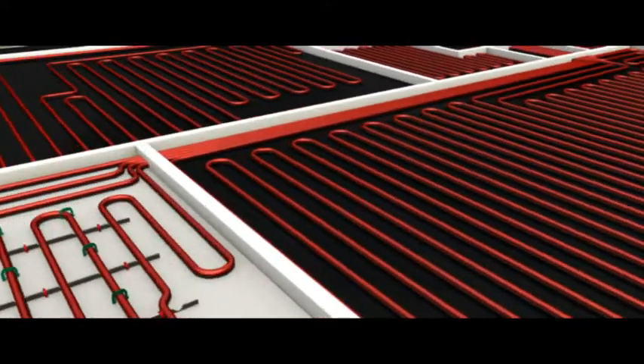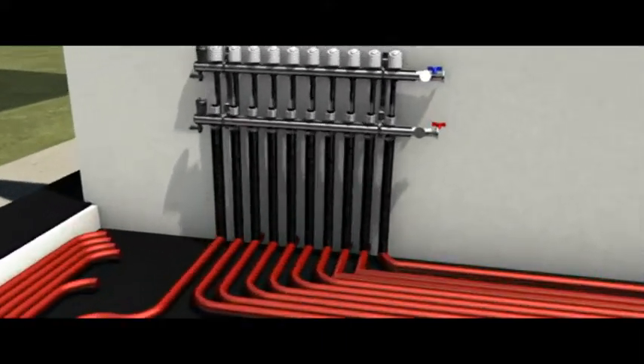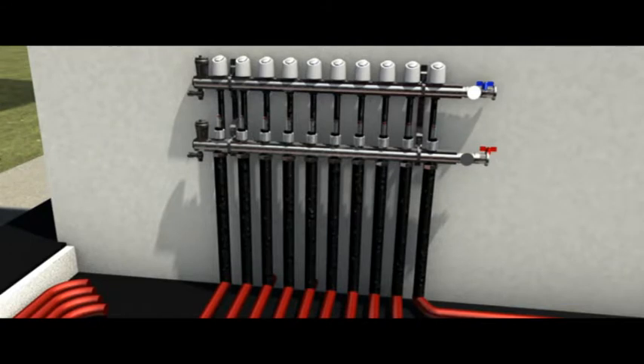Only when all the pipes are laid and run back to the manifold can they be pressure tested to ensure that the pipe has not been damaged during the installation process. The pipes can be tested through the manifold using either air or water, depending on local weather conditions.